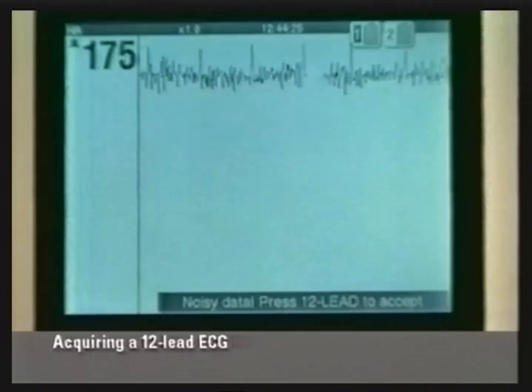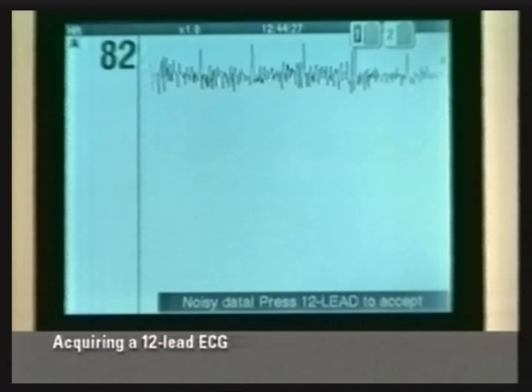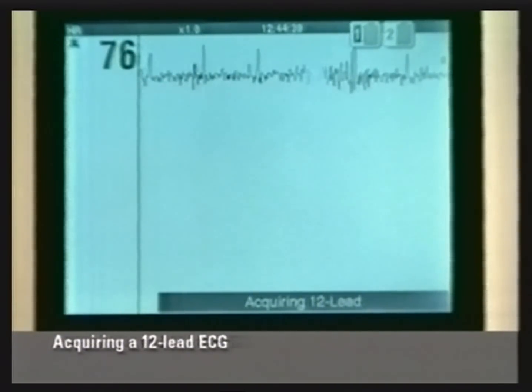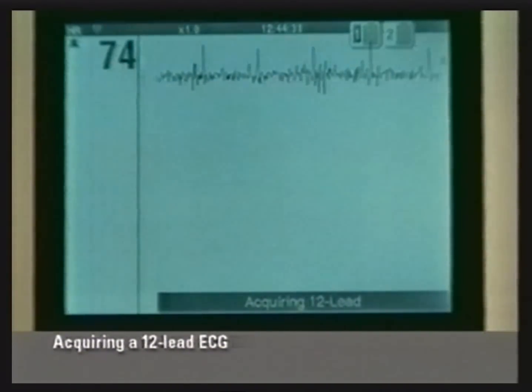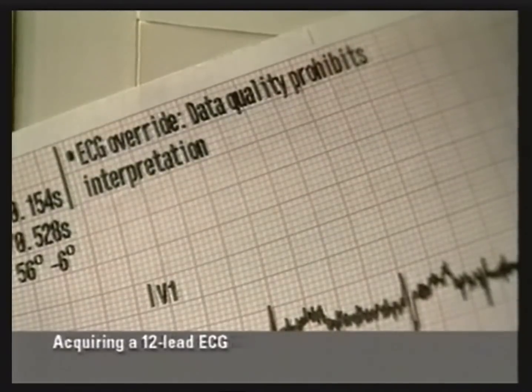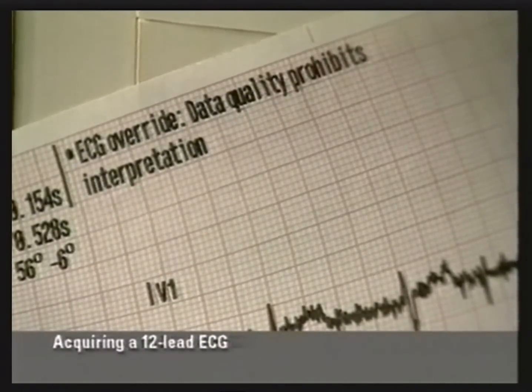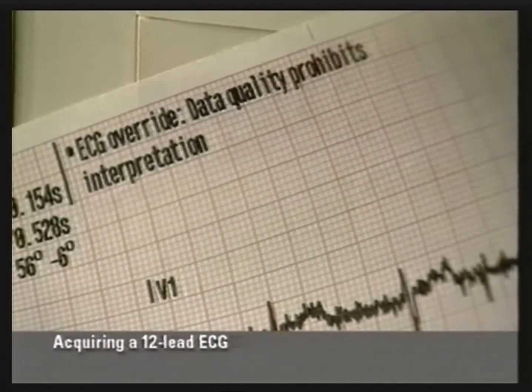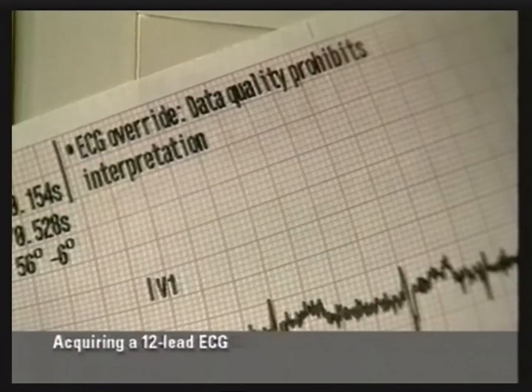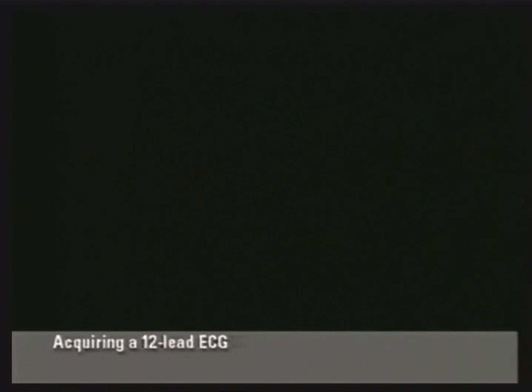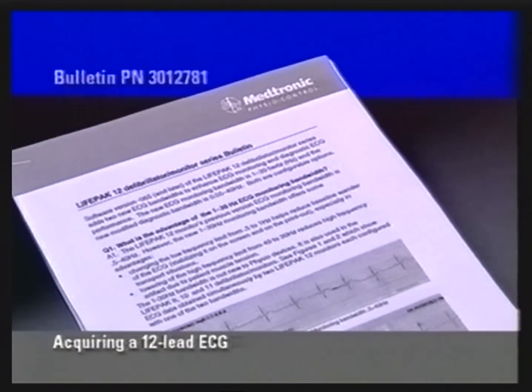If you are unable to clear the noisy data message, press 12-lead a second time. This forces the monitor to acquire the data in spite of a noisy signal. Any 12-lead ECG reports acquired in this way are annotated with the message, "ECG override, data quality prohibits interpretation." For more information about troubleshooting ECG noise, request a copy of the Lifepak 12 Bulletin about ECG bandwidths and ECG troubleshooting.